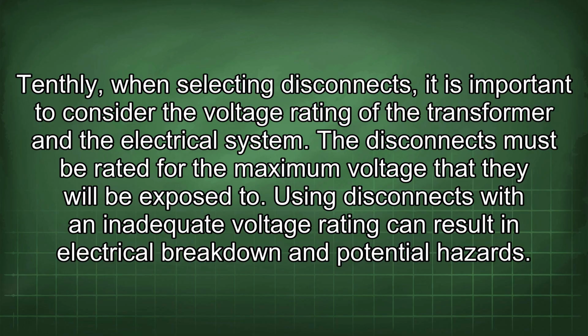Tenthly, when selecting disconnects, it is important to consider the voltage rating of the transformer and the electrical system. The disconnects must be rated for the maximum voltage that they will be exposed to. Using disconnects with an inadequate voltage rating can result in electrical breakdown and potential hazards.